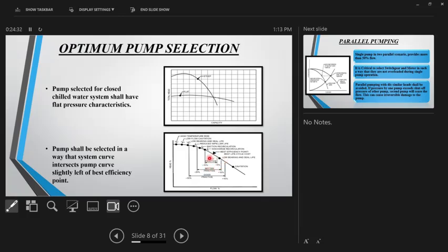That's the best practice. If for some reason you can't do that, they have also given a better practice, which is a slightly larger range, and a good practice, which is again a much larger range. So if you really deduce this graph, you should not go right of plus 15% of BEP, the best efficiency point, nor less than minus 30% of the flow at the best efficiency point. If you could select the pump within the best practice, better practice, or good practice at worst, you are likely to get good working of the pump. Anything beyond these ranges, you are actually endangering your pump in terms of its life.